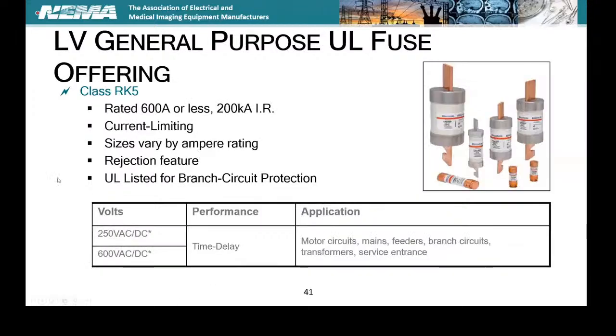RK5s, now you're getting into current limiting solutions. There's rejection features. You'll see that on the tongue, or whatever you want to call that. There's a little notch on that blade where it goes into the holder, and the Class H or the previous class did not have that notch, so you wouldn't be able to put a non-current limiting device into a switch or holder that is notched out so that it will accept that fuse. That's what we call the rejection feature. Some of these fuses will reject based upon a little notch like that. Others will reject based upon the size or other little nubs on the top. Like the smaller ones at the bottom right, there's a little cup down there that's like a lip. That's the rejection feature on those. So you may have different styles depending upon the holder.